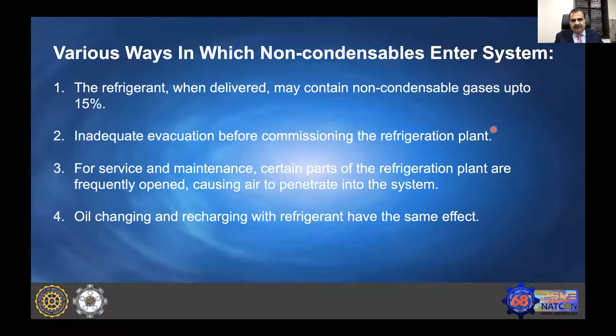Secondly, when our plants are running at low temperature applications, particularly below atmospheric pressure, that is at minus 30, 33 degrees centigrade, and low temperature plants, if there is a leakage into the pipes, glands, valve stems, bonnets, etc., then ammonia will not come out, particularly on the evaporator side, the low side, but the air will go in because the internal pressure is lower than the outside pressure. That's one big way of entering air into the system.